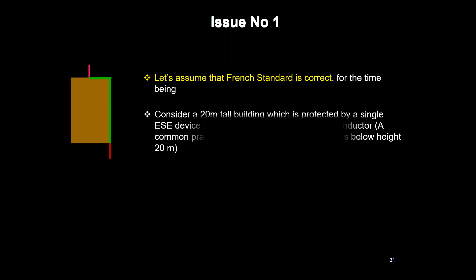But still there is a problem. Now, up to about 20 meters, they recommend one down conductor. This is one catch point or attractive point of ESE technology, because they say just one down conductor, so it is very convenient for the installer as well as the lightning protection seeker.